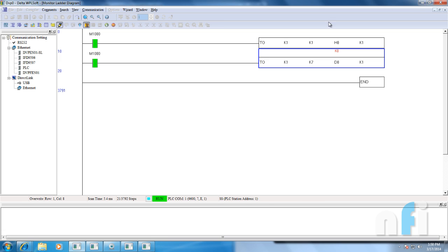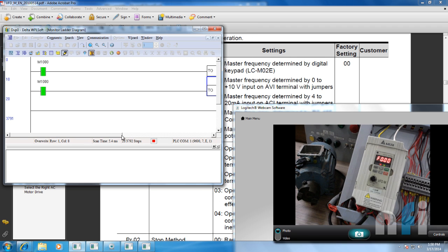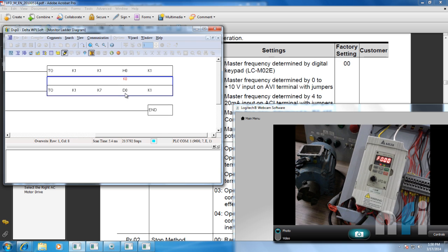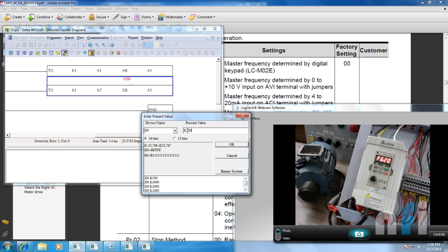I've taken a variable D0 here for the source of frequency — right now it's K0, so the output is 0 volts and frequency is 0 Hz. If I change the value to K1000, you'll find the frequency changes to 12.6 Hz. If I put 2000, frequency will change to 25 Hz because that's 5 volts. If you put 4000, frequency will change to 50 Hz. Let's roll back to 500 — that will be about 6.3 Hz. Now if I start the drive it will start running and the frequency of the motor will change in real time.